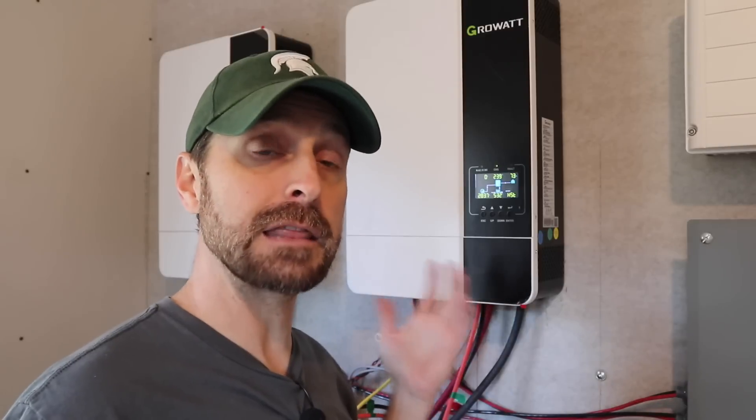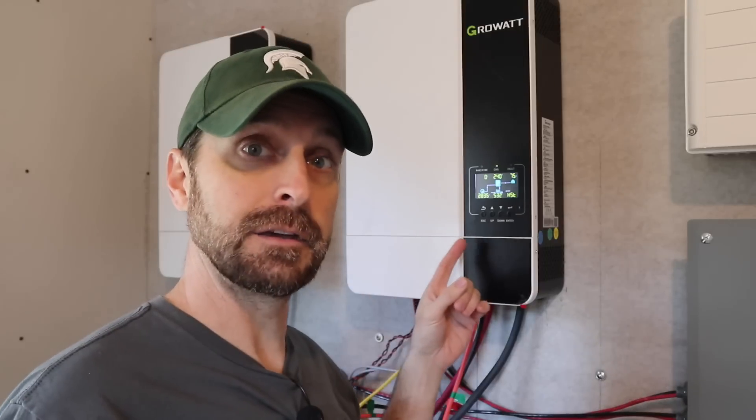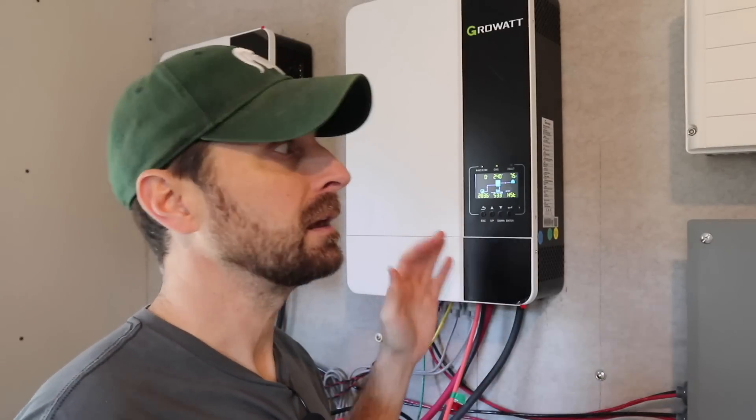You off-gridders out there know that you're never going to have all these loads on at the exact same time, nor should you. You should be smart about how you use your solar system. I just want to remind everyone that these Growatt 5000ES inverters I got from Signature Solar, who is an authorized dealer, are modified for our American grid — modified at the manufacturer. There are other Growatt 5000ES models being imported that are not internally modified, and those could be dangerous. So only buy these from a reputable authorized Growatt dealer. These off-grid inverters have the ability to take AC into them, but I'm keeping them strictly off-grid.